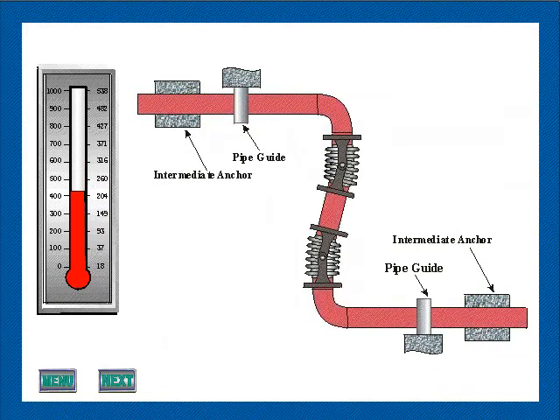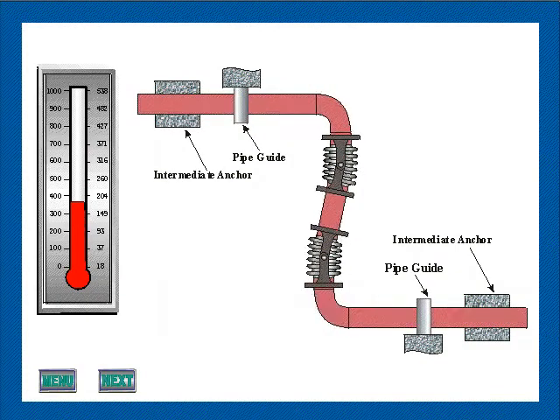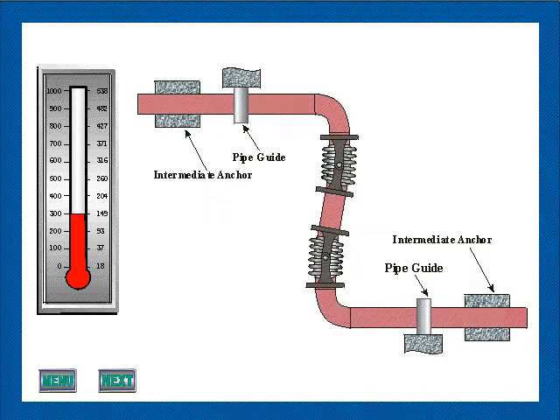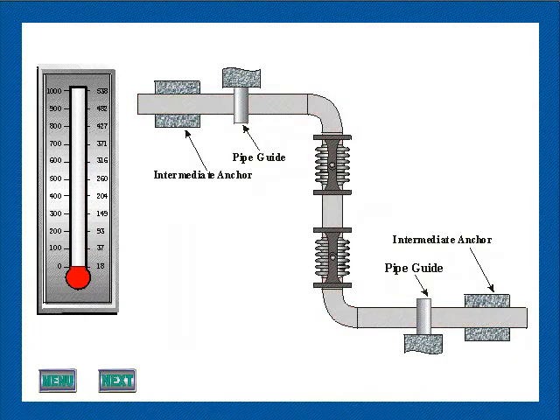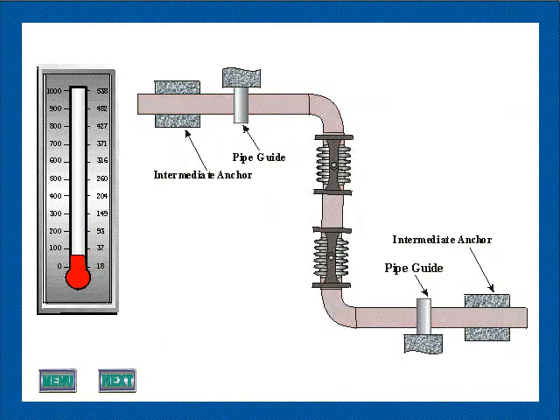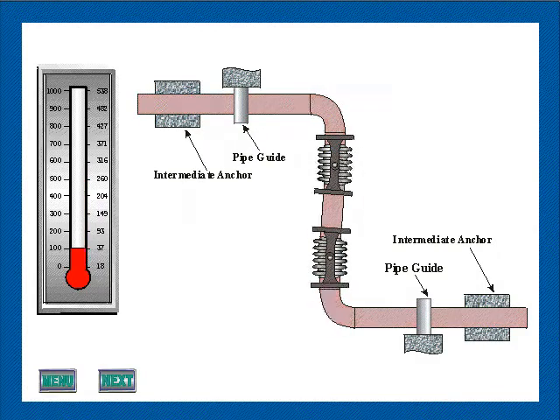In calculating guide clearances, consideration shall be given to the fact that the thermal expansion of the offset piping leg containing the expansion joints will be partially offset by the reduction in length resulting from the displacement of the center pipe section. This effect may be neglected only where the distance between the hinge pins is very large and the lateral displacement is small.